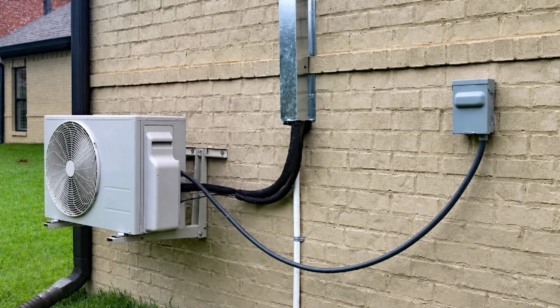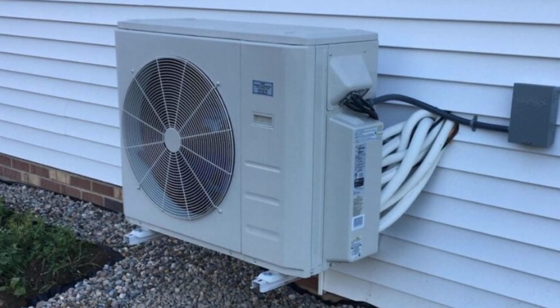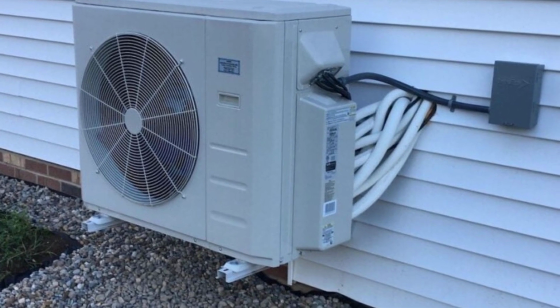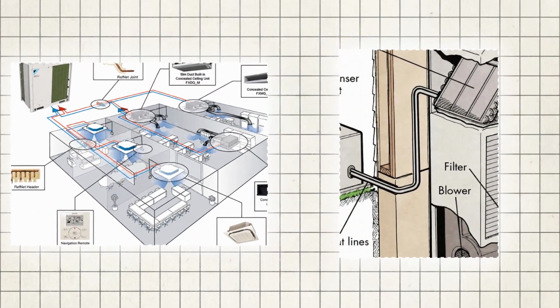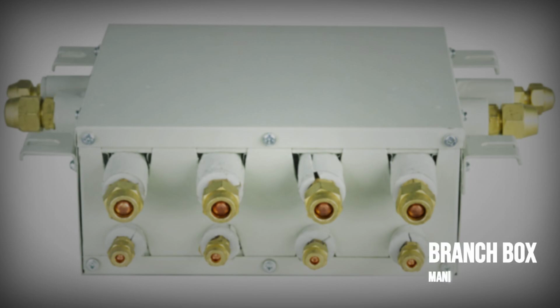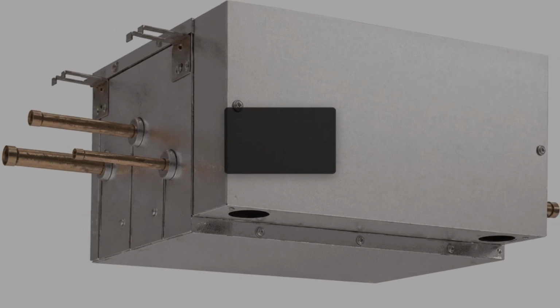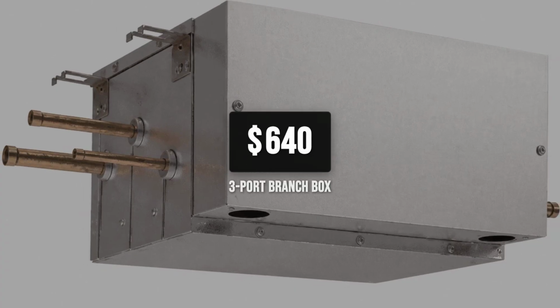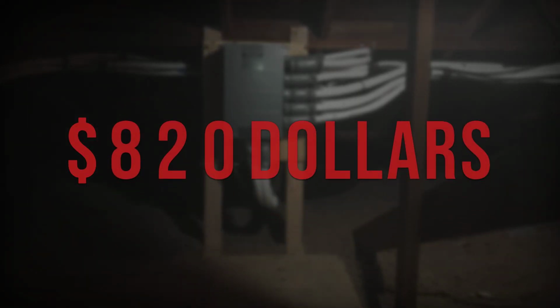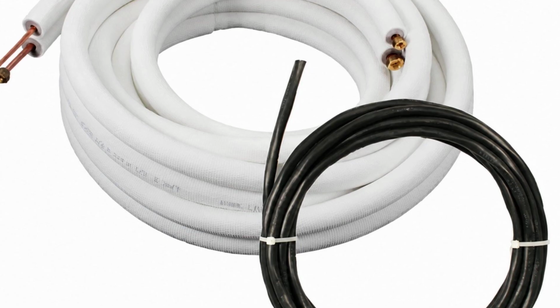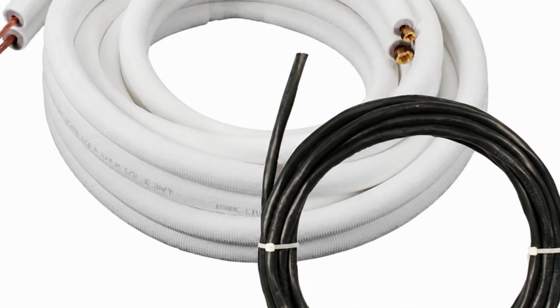Number 2. The part that never shows up on the invoice. A multi-zone system isn't one machine with extra heads. It's a refrigerant network, and networks need hardware central doesn't. Start with the branch box, a sealed manifold that splits refrigerant to each head. One manufacturer's 3-port version lists near $640. The 5-port lists near $820. But that's before labor.